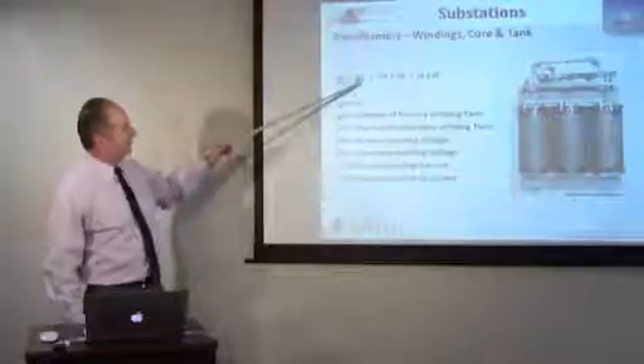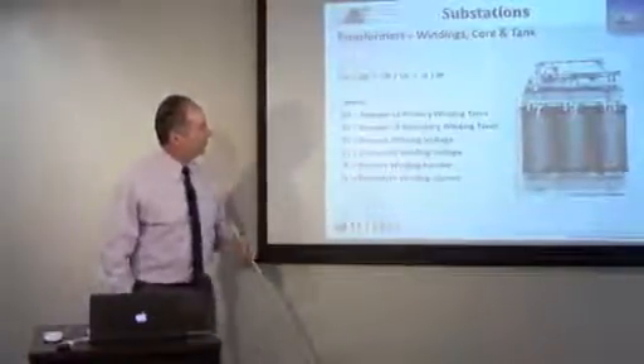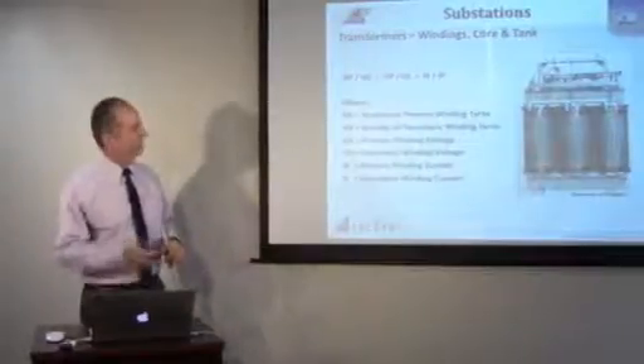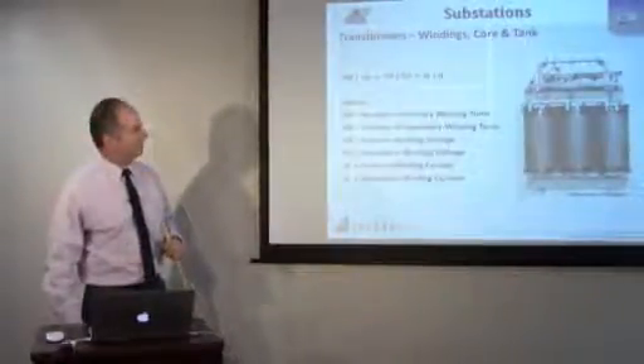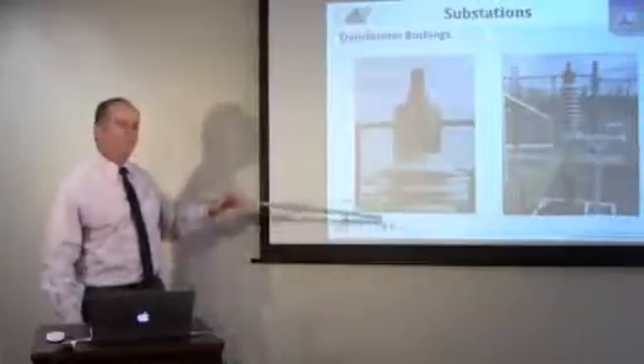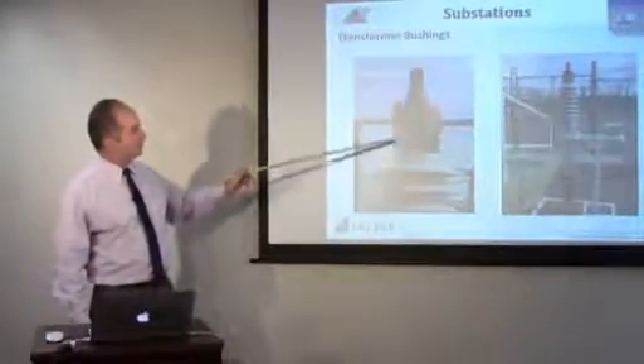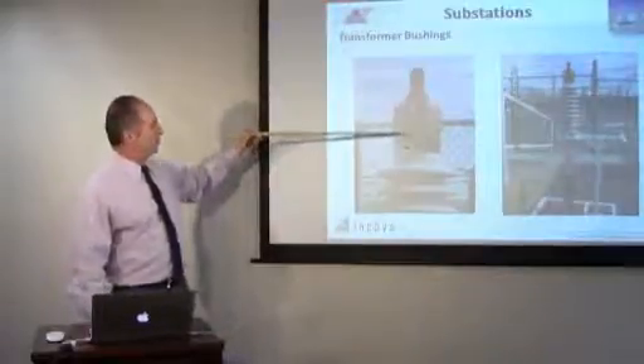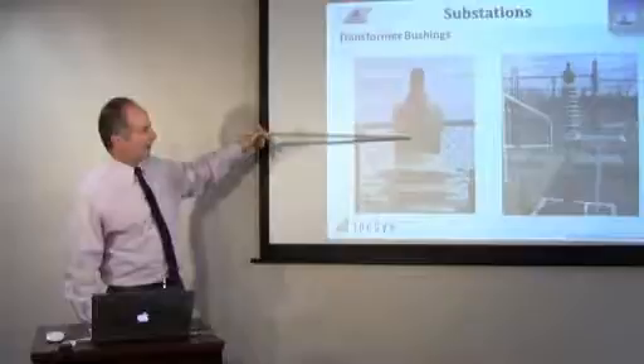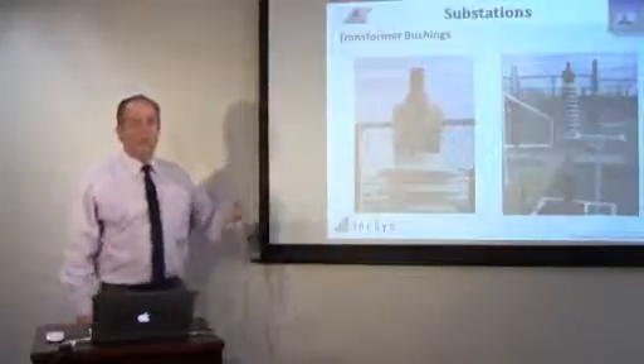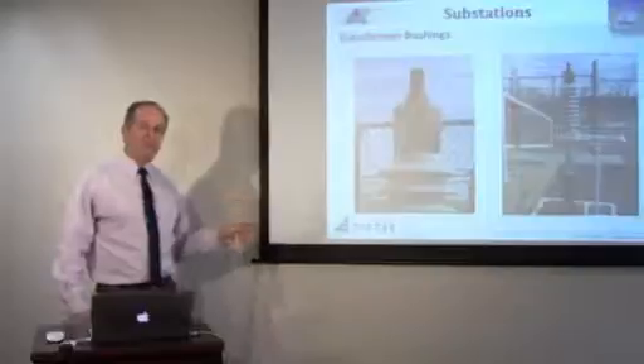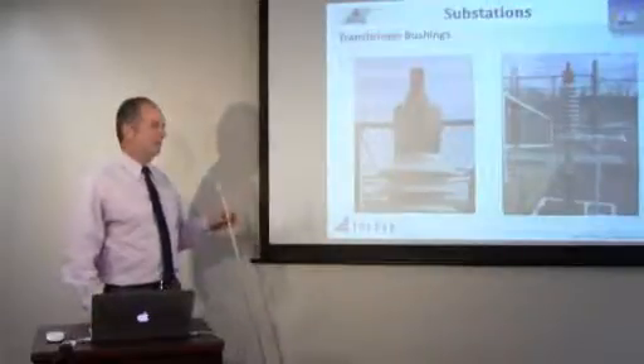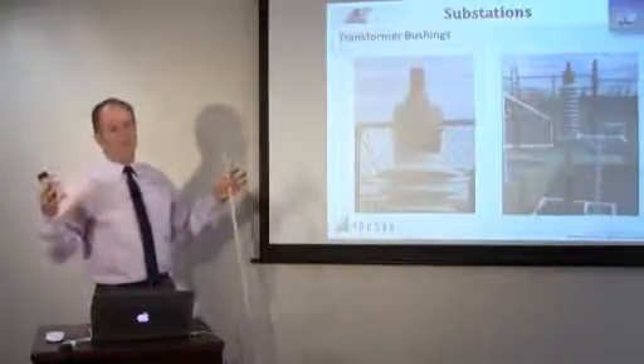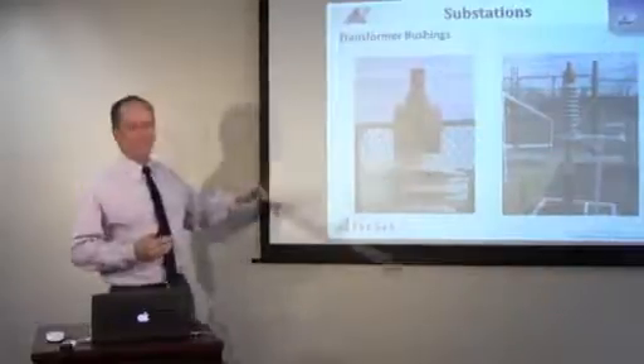Now this drawing is showing some of the different ratios. We talked about the primary ones being the voltage ratio and the current ratio. Here's a bushing. This particular bushing is a close-up. I want you to notice there's an oil level in here that lets you know that there's oil in the bushing. Now remember, oil is an insulator, and if you lose the oil in a bushing, you could easily destroy it, and it could blow up. It could be shrapnel-type glass, porcelain blowing up all around.